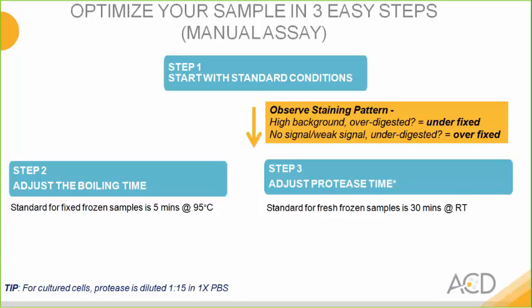Now, in order to address these issues, you would either adjust the boiling time. This would certainly be applicable to fixed samples, the fixed frozen and the FFPE samples. For fixed frozen samples, the standard is 5 minutes. For FFPE, the standard is 15 minutes, so you can certainly adjust that. As far as fresh frozen samples go, you can adjust the protease time. The standard is 30 minutes at room temperature.